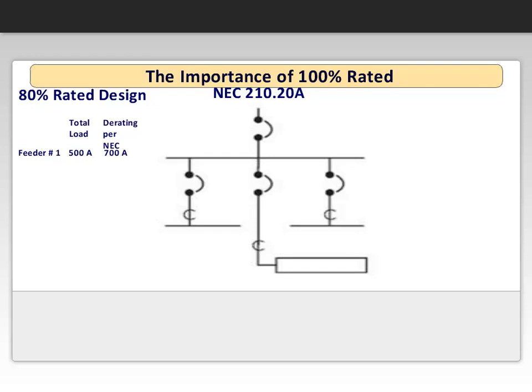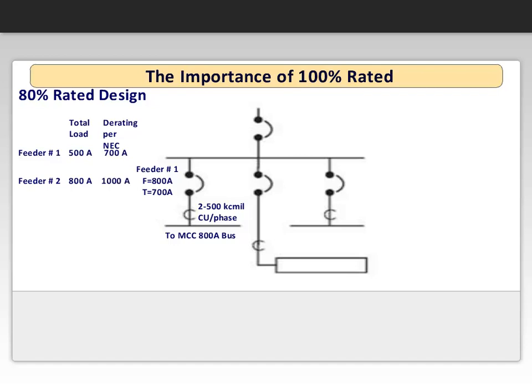Since there are no 700 amp frame standard breakers, we must use an 800 amp frame with a 700 amp trip. Thus, the cable feeding this motor control center must be sized for the 700 amp trip, making it 2 500 kcmil copper wires per phase. And the motor control center bus must be rated at 800 amps. It is determined that feeder number 2's load is 800 amps. Using the same derating process, we end up using 1000 amps, making it necessary to use a 1200 amp frame and a 1000 amp trip unit.